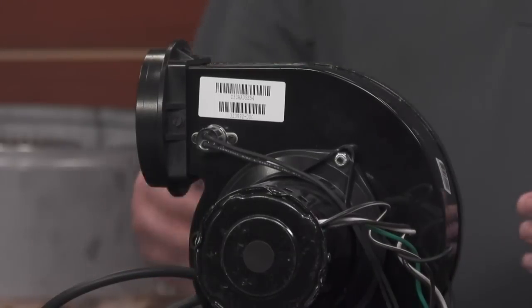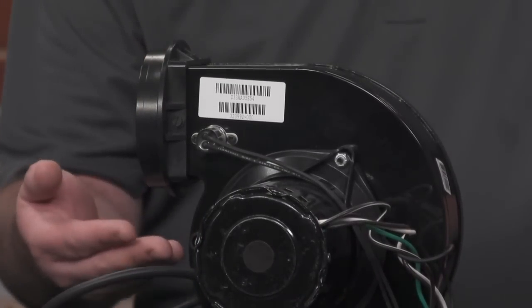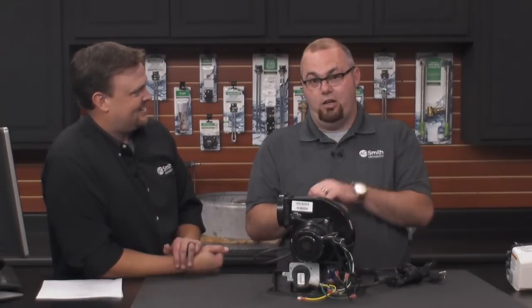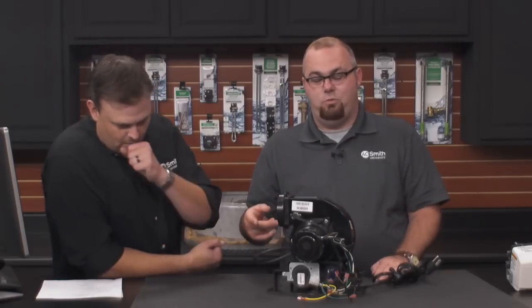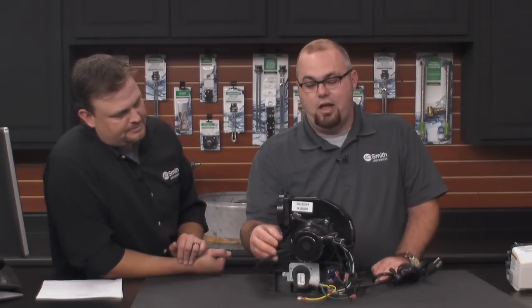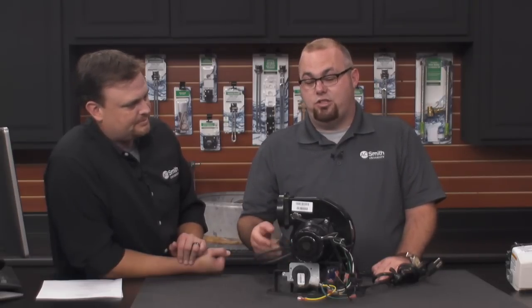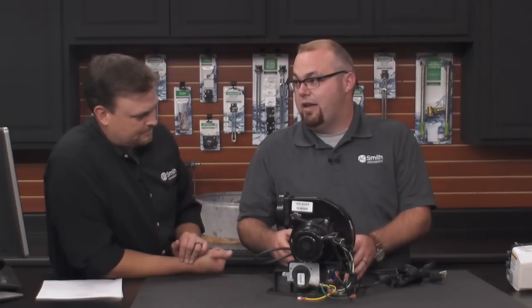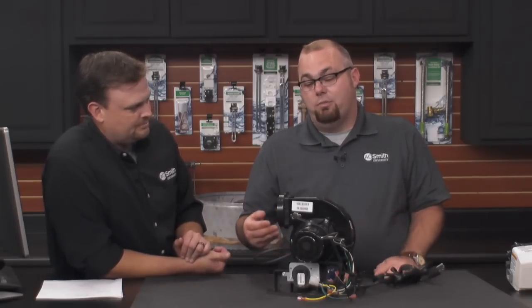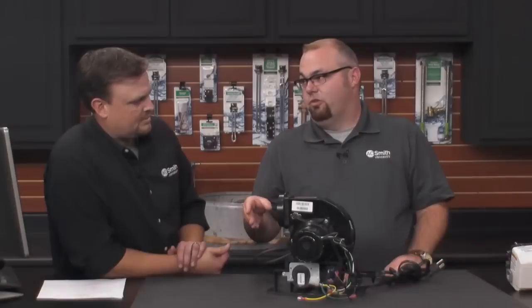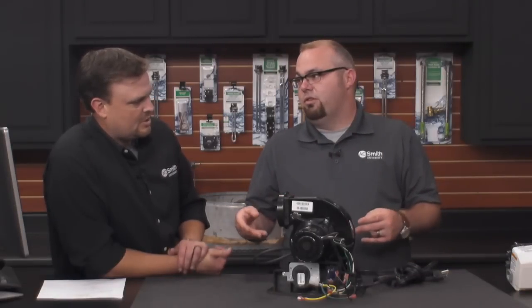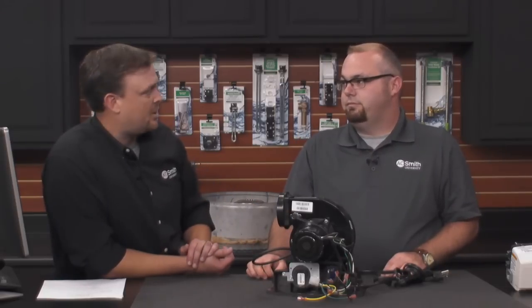Correct, and this one's actually a normally open switch. The air pressure switch on this water heater, the blower prover, is an open switch that closes on a fall in pressure when the blower creates a vacuum as it turns. But wired in series with that switch is a vent temperature high limit switch that ensures that if the blower were to get too hot, it would not melt the venting. It'll shut the water heater off. The important reason to know why they're wired together is that if one opens, the control valve is going to see it as the same thing. It's just going to give you one code. It cannot differentiate between whether it's the vent limit switch open or the blower prover switch open. So you have to be able to check them both. You don't want to forget about it. That switch will actually open up at 145 degrees.